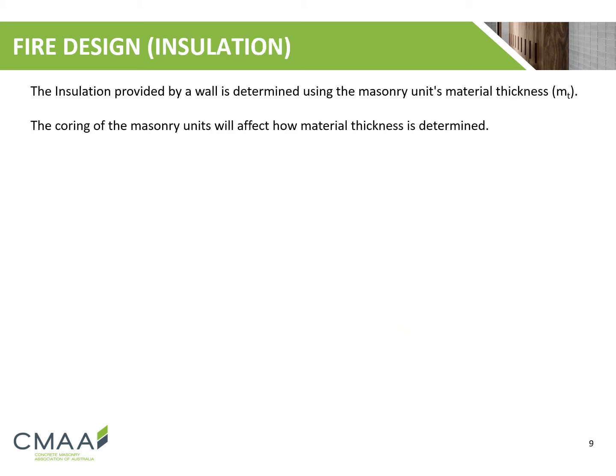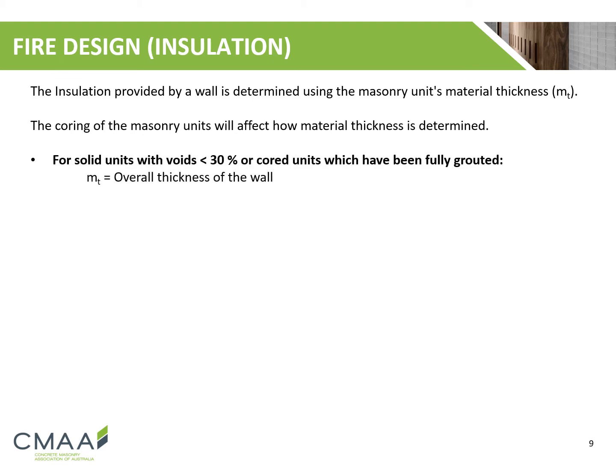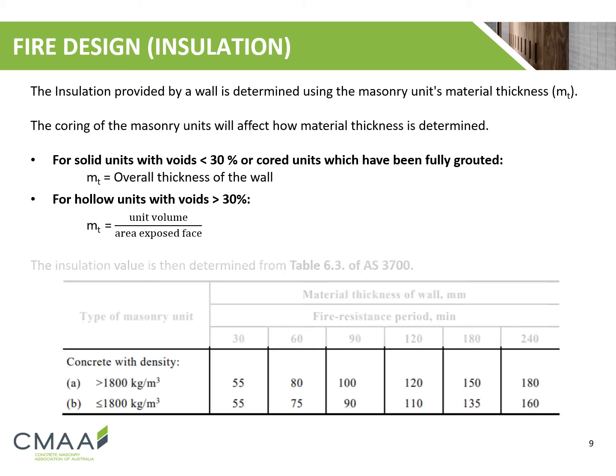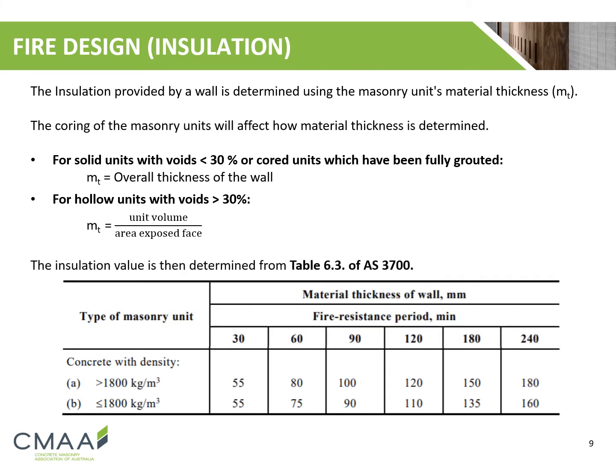The insulation provided by a wall is determined by the masonry unit's material thickness. Coring of masonry units will affect how the material thickness is determined. For solid units with voids smaller than 30%, or cored units which have been fully grouted, the material thickness is equal to the overall thickness of the wall. For hollow units with voids greater than 30%, the material thickness is equal to the unit volume divided by the area of the exposed face. Once material thickness is determined, Table 6.3 of AS 3700 can be used to identify the insulation fire resistance period.